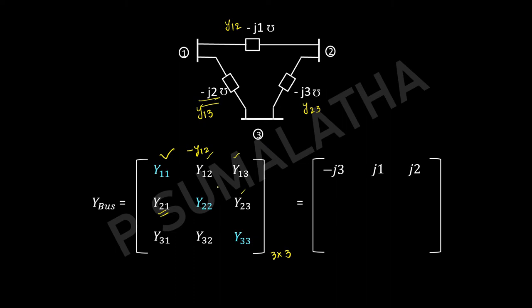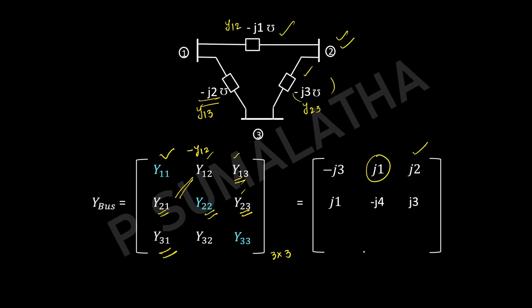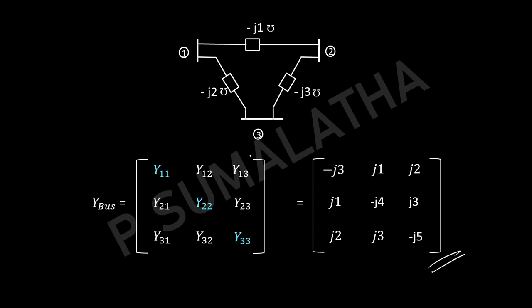Y21 equals Y12, so it is plus J1. Y22 is the sum of admittances connected to the second bus — two lines are connected — giving minus J4. Y23 equals minus of Y23, so plus J3. Y31 equals Y13, so it is plus J2. Y32 equals Y23, so that is plus J3. Y33 equals the sum of admittances connected to the third bus: minus J2 plus minus J3 equals minus J5. This is how we form the bus admittance matrix using the inspection method.